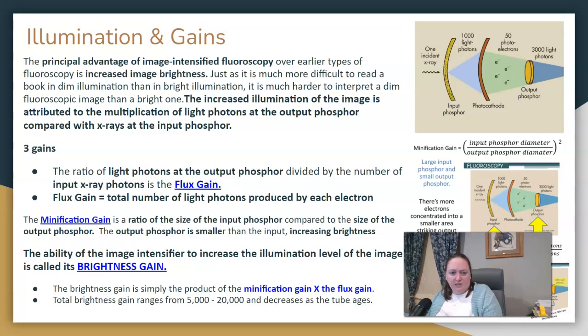Minification gain is a ratio of the size of the input phosphor compared to the size of the output phosphor. Well, the output phosphor, spoiler alert, always smaller. So we are gaining in minification, right? So remember those electrostatic lenses that focus that beam down smaller? If you think of that, we go from a large input down to a smaller output.